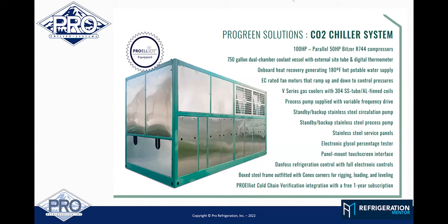On our gas coolers, which are up in the perforated sheet metal end of the system, we run EC fan motors on the header fans and AC fan motors on the back fans. That way we can use the EC fans when ambient temperatures allow, really bringing those pressures down.